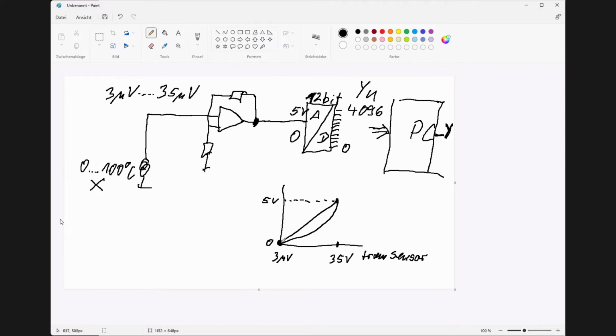We look that the zero point is clear: the lowest point and the highest point must fit to the output voltage. When we have a huge error, we have to calibrate it step by step with linear functions. We approximate with linear functions and calibrate this function to the true curve. How we do that, I will explain with an example.